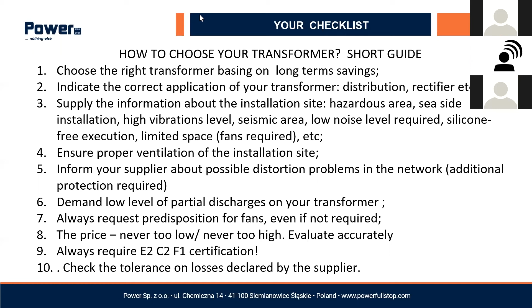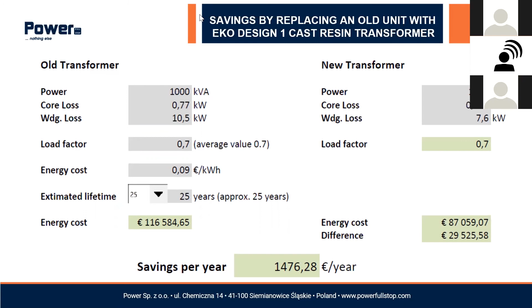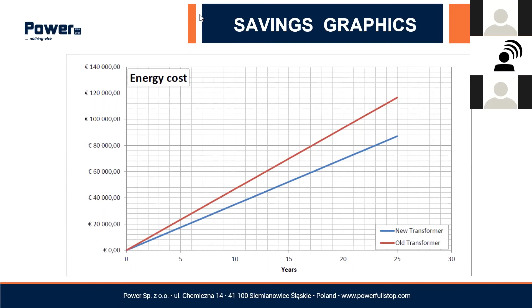So just a short comparison between an old, not eco-design transformer and a new tier 1 transformer, in this case. As you can see, in 25 years you save something like 30,000 euro, so it's a quite nice medium class car, we can say. This step has been done in 2015, and I think we could not wait anymore. These savings are not that extreme with tier 2, of course, but the first step has been done. So replacing old transformers with new eco-design transformers really means saving a lot of money over time.